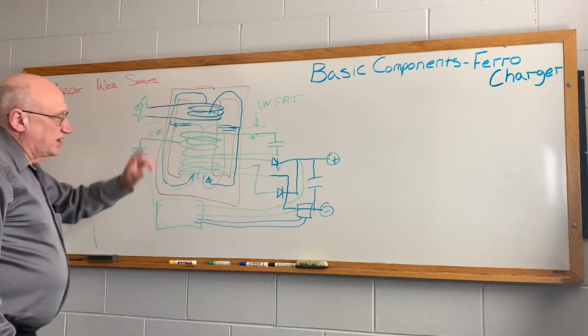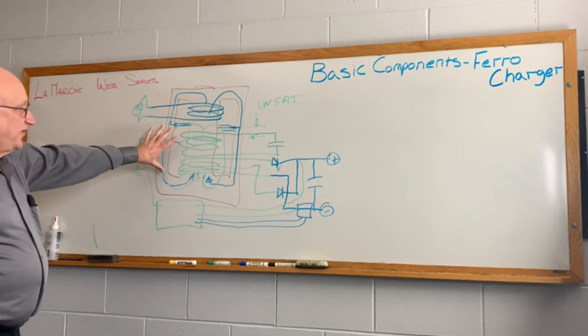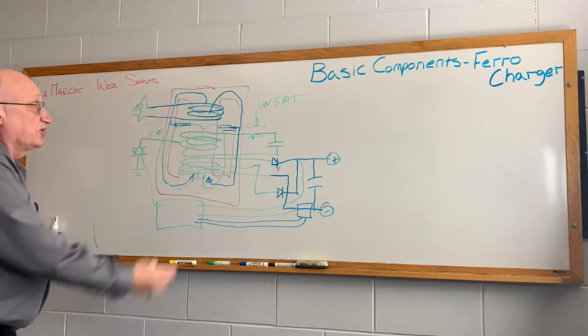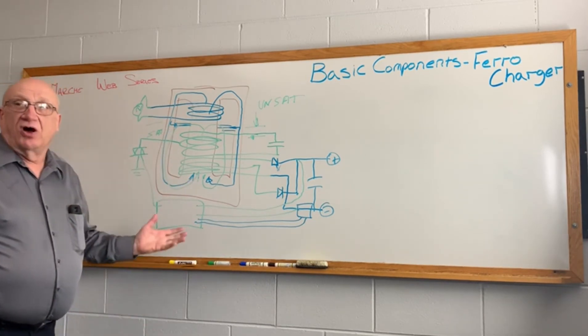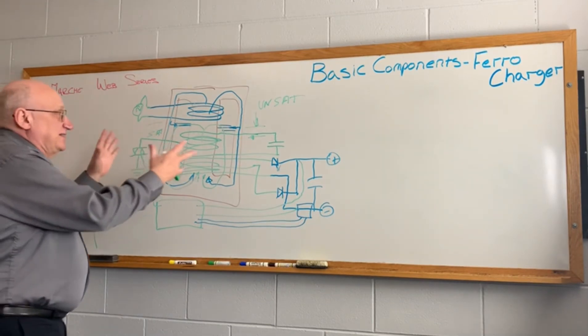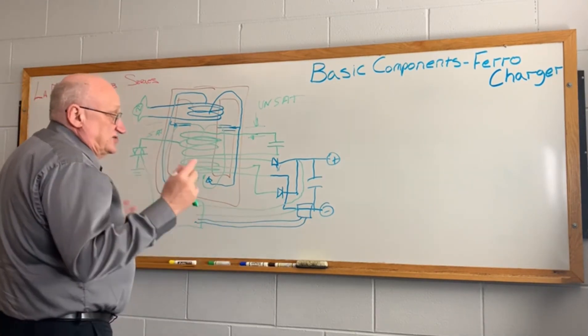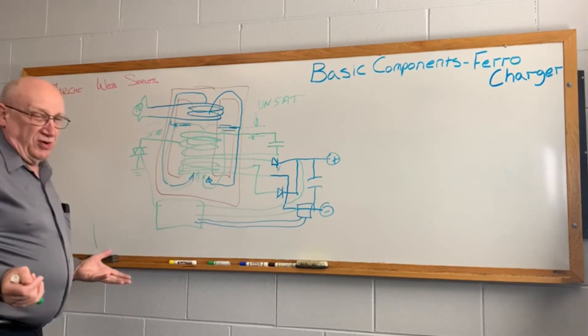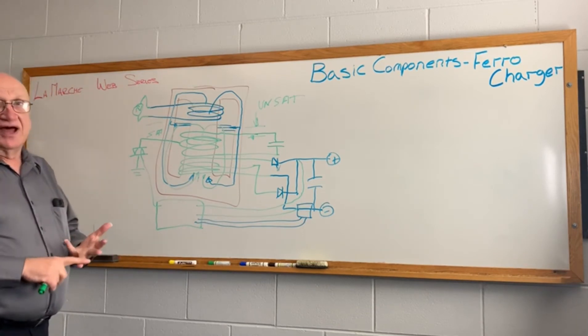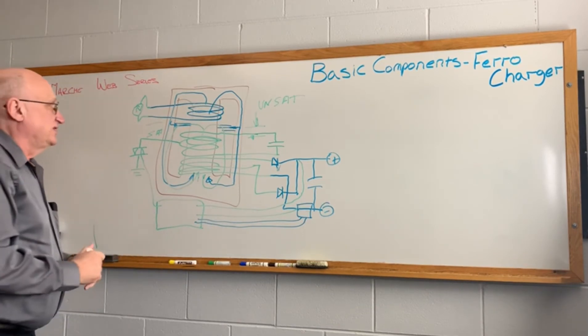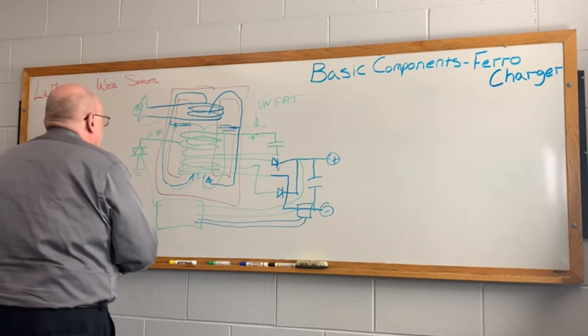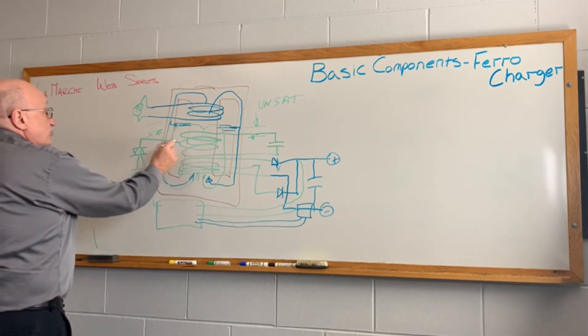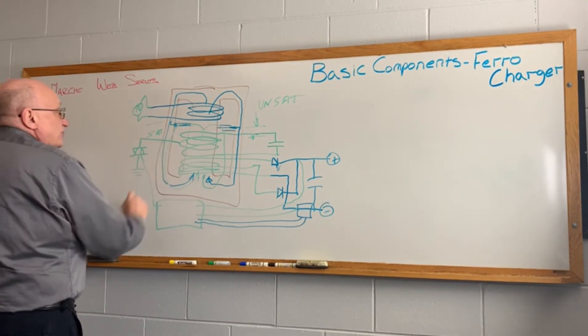The difficulty with the ferro uncontrolled is there's no adjustment. It's all run and stated by what you got for the steel. So you need some control and adjustment for float and equalize, for current limit, etc. So how do you do that? By adding a triac on the resonant winding.